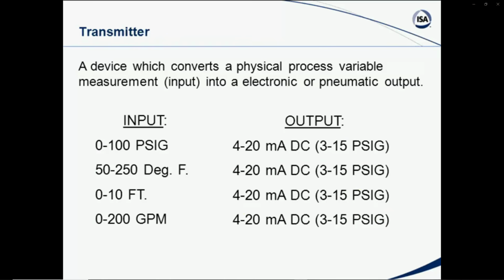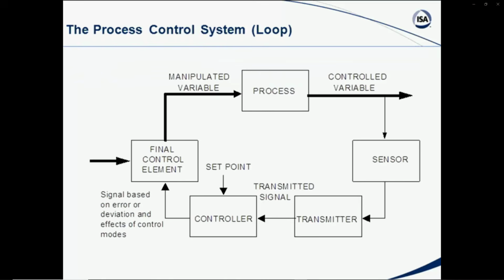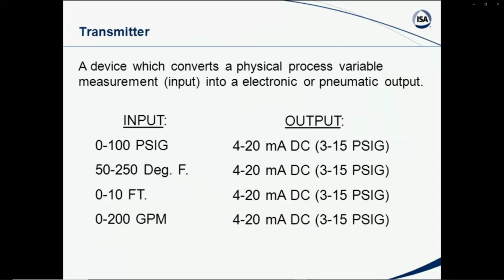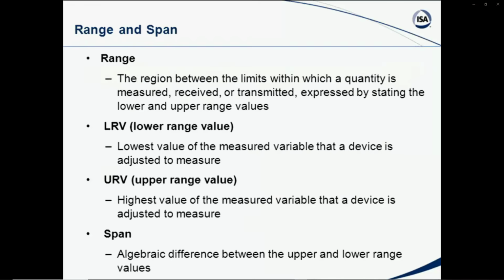So what we're doing here is taking a physical process variable, putting that into some form that we can use as the intelligence and data for our control system to affect our process control. And we'll be talking a lot, at least initially, basically, as we looked at on the prior slide, in the form of what we would call regulatory feedback control. This is regulatory feedback control. As we go through the seminars, we will change this somewhat and go to some other types. But this is feedback regulatory control that we will be looking at for the most part. And the sensors and the transmitters are those devices that give us that intelligence for our control system. So that's how we go about it to begin with.